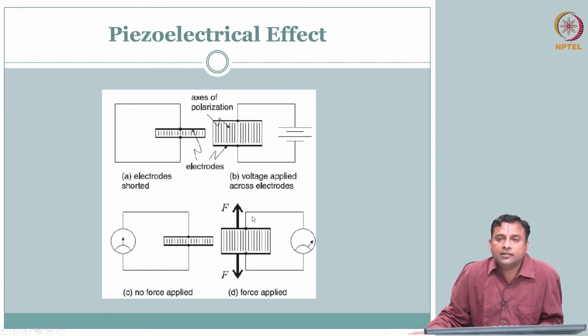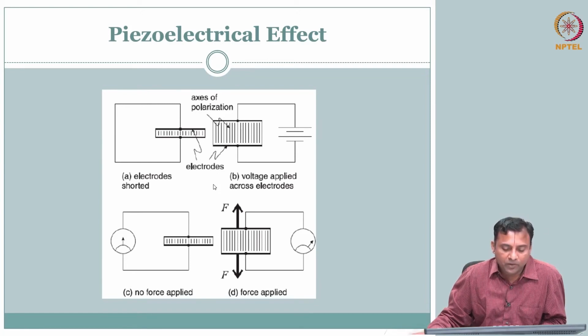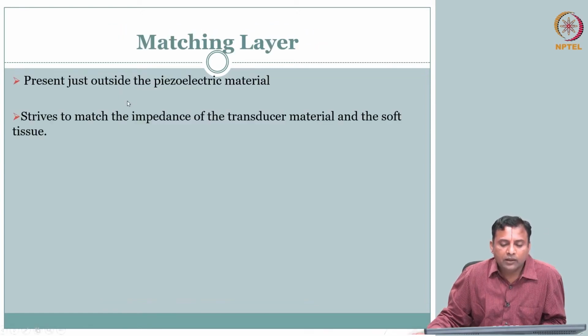So we will just appreciate that this is a good crystal, that this crystal is providing us with the ability to generate the compressional wave of a desirable frequency, and also has the ability to detect this compressional wave and convert it to an electrical signal with a reasonable efficiency, right. The conversion loss from one form to the other is still not too much that it makes it useless. Okay. So we will do that.